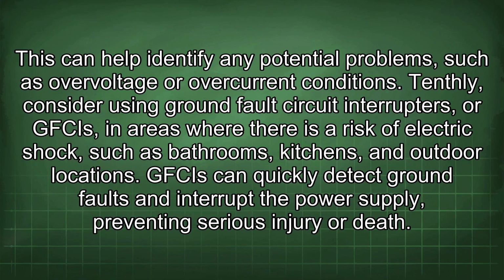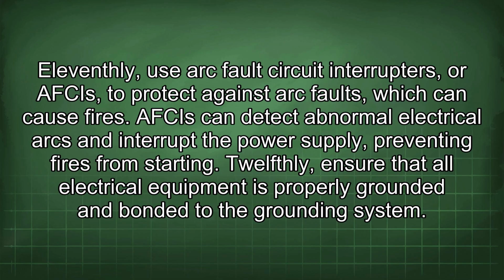Tenthly, consider using ground fault circuit interrupters, or GFCIs, in areas where there is a risk of electric shock, such as bathrooms, kitchens, and outdoor locations. GFCIs can quickly detect ground faults and interrupt the power supply, preventing serious injury or death. 11thly, use arc fault circuit interrupters, or AFCIs, to protect against arc faults, which can cause fires. AFCIs can detect abnormal electrical arcs and interrupt the power supply, preventing fires from starting.